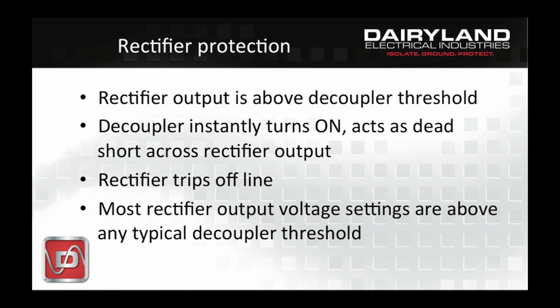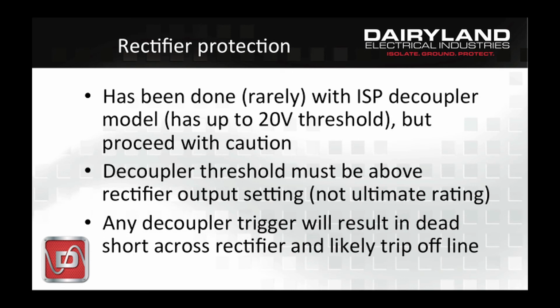With the rectifier output being above the decoupler threshold, the decoupler is instantly going to turn on. It's going to look like a dead short across the rectifier terminals, and the clearing device, such as a breaker or a fuse, is instantly going to take the rectifier offline. So there's no more CP output from the rectifier. Now, most rectifier settings are going to be above any reasonable decoupler threshold, so this is not likely a solution in any case.